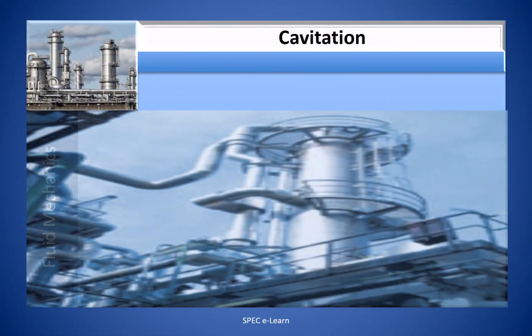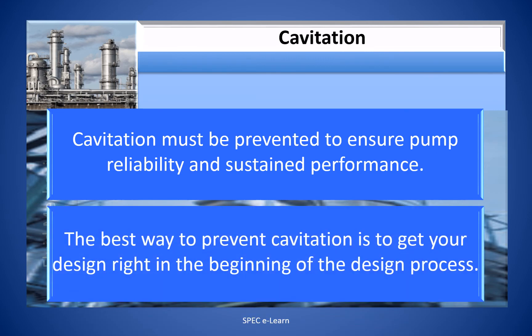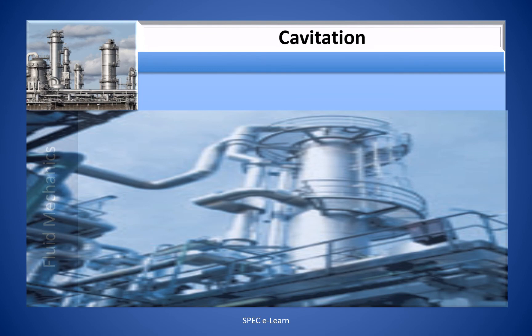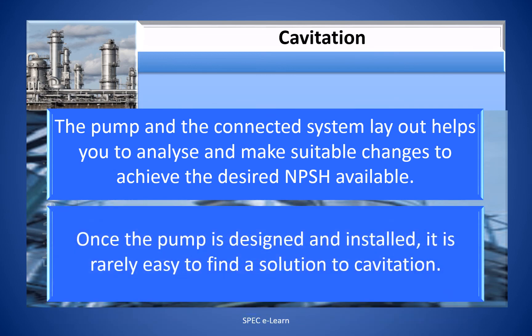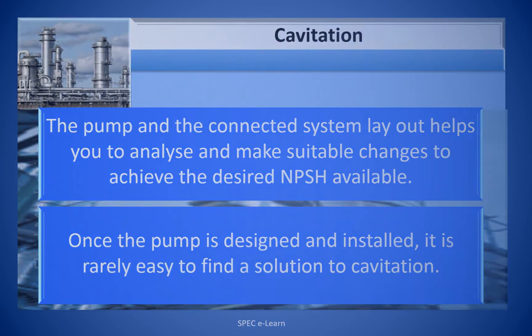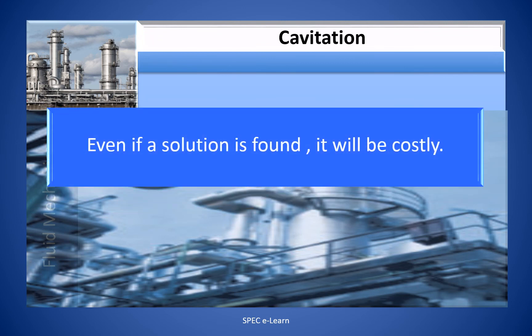The key takeaways from this discussion: cavitation must be prevented to ensure pump reliability and sustained performance. The best way to prevent cavitation is to get the design right at the beginning of the design process. The pump and the connected system layout help you analyze and make suitable changes to achieve the desired NPSH available. Once the pump is designed and installed, it is not easy to find a solution to cavitation, and even if a solution is found, it will be costly.